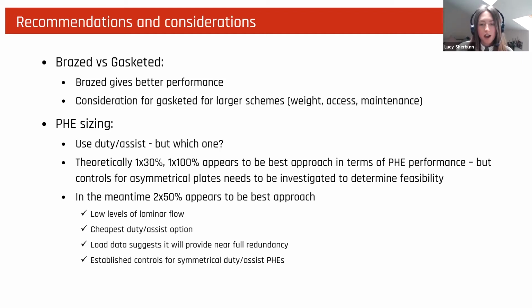Plate heat exchanger sizing, I think it was kind of clear that using a plate sized at 100% is probably not the way to go. So that leaves the duty assist options, but which one? Well, theoretically, using a jockey plate appeared to be the best approach in terms of flow performance, but we haven't really seen this approach used on site or have experience with it. So we need to investigate and determine feasibility of using these asymmetrical plates. So in the meantime, using 2 plates sized at 50% appears to be the best approach.